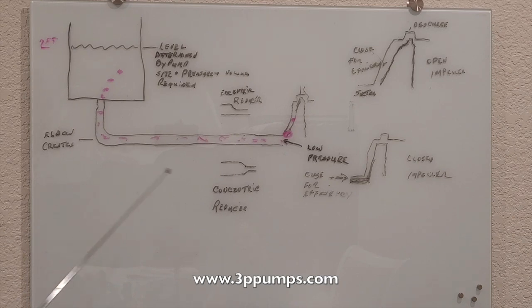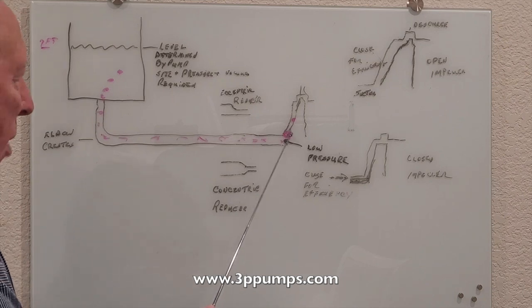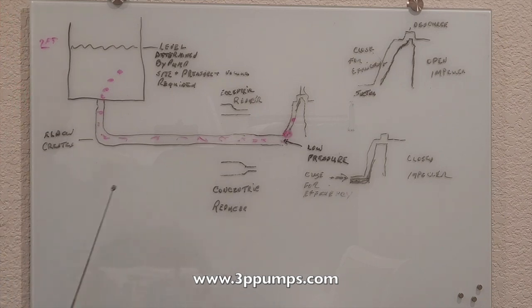Now, cavitation a lot of times is explained to hear it. It sounds like marbles running through your pump. And basically what that is, is all these minor explosions in there, and those minor explosions are causing the pump to vibrate. This low pressure out here also causes a vacuum which tries to pull water through your seal on the other side in your stuffing box over here, and we'll get into that in a minute, okay? So you've got a complete problem here caused by low pressure.